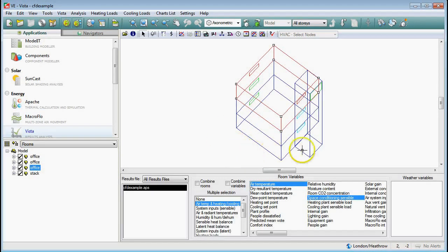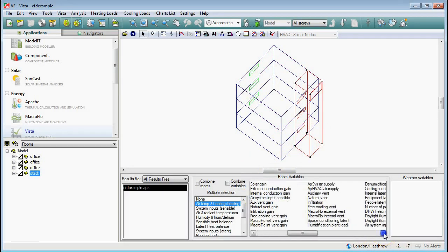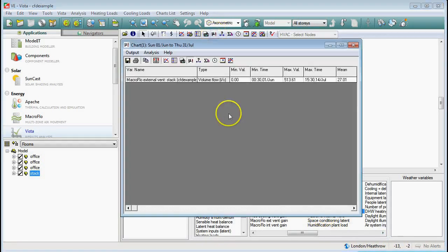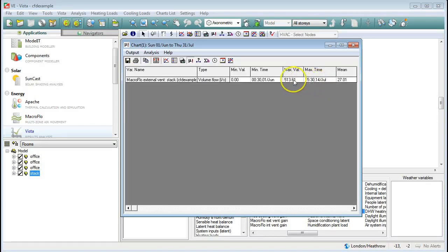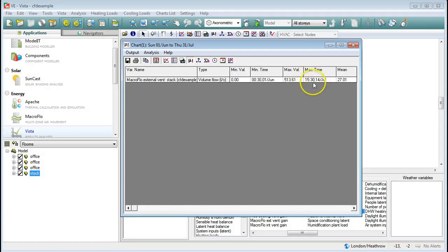What I'm going to do is have a look at the chimney stack here and look at the external ventilation - the macro flow external ventilation - and see when is the maximum flow time. The time of maximum flow through the ventilation stack is at half past three on the 14th of July. I'm picking that maximum time because as part of my CFD analysis I have to pick an instance to simulate, so I'm picking the time of maximum ventilation.